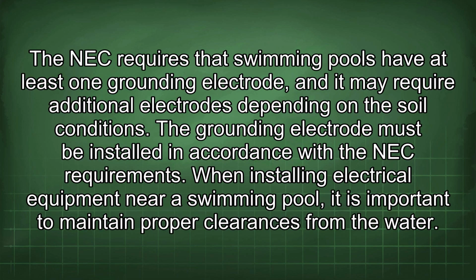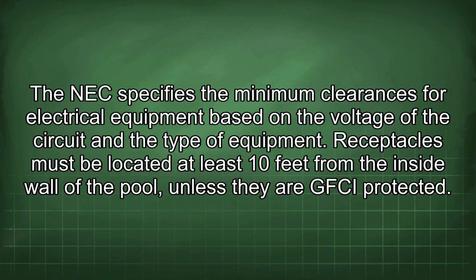Grounding electrodes, such as ground rods or ground plates, are used to provide a connection to the earth. The NEC requires that swimming pools have at least one grounding electrode, and it may require additional electrodes depending on the soil conditions. The grounding electrode must be installed in accordance with the NEC requirements. When installing electrical equipment near a swimming pool, it is important to maintain proper clearances from the water. The NEC specifies the minimum clearances for electrical equipment based on the voltage of the circuit and the type of equipment.